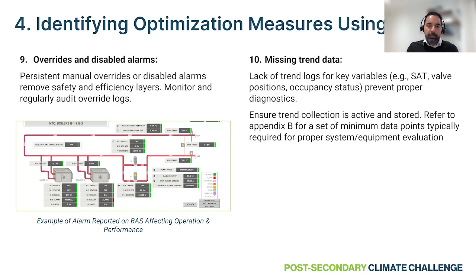And one of the other things that we noticed in some cases where we did the analysis is that a lot of the trends were missing. Either they're not set up or they're not archived properly. So the fundamental thing about understanding the performance of the building is ensuring that these trends are available for somebody to historically look at the issues, and that helps you with the diagnostics of these systems. So ensure that you have a minimum trend set up, and that those trends are archived for at least a year so that you can go back and take a look at those issues as well.